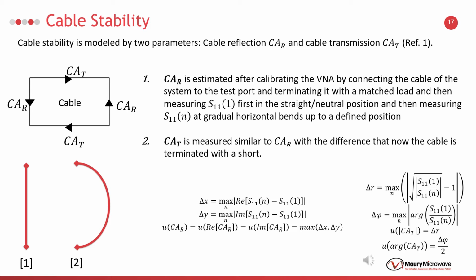Cable stability is modeled by two parameters, cable reflection and cable transmission. To calculate the cable reflection, the cable is terminated with a matched load, and S11 is measured with the cable in a neutral position at first. Then the cable position is changed, and S11 is measured again. After several measurements with different cable positions, the maximum deviation of real and imaginary parts of S11 is considered as cable's reflection uncertainty parameter. Cable transmission is also calculated in the same way, but with a short termination. Maximum deviation of the phase and magnitude of S11 values are considered as uncertainty parameters of cable transmission.